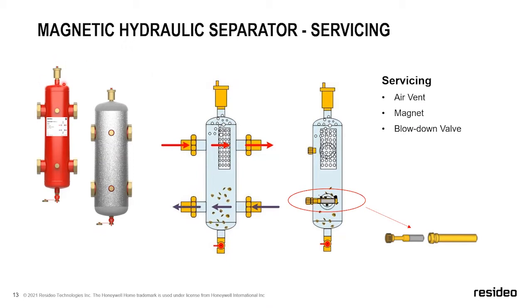So what we've done is we have two different methods for serviceability on this. One, our residential, our union models, so that's the sizes 1 inch through 2 inch, and I'll go into the size offering in a minute. We have installed a check valve assembly right here. So the way this works is when the air vent is screwed in, it's pushing that check down so that the air and water can come up.